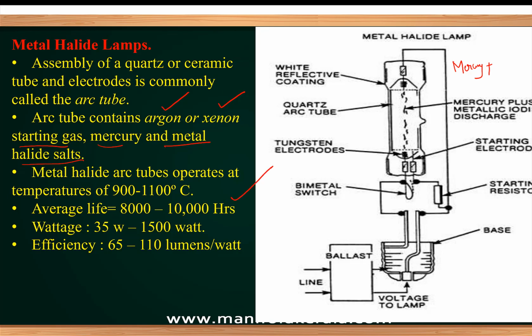Average life is given. Wattage: they are available in a wide range of wattage from 35 to 1500 watt. Luminous efficiency is between 65 to 110 lumen per watt.